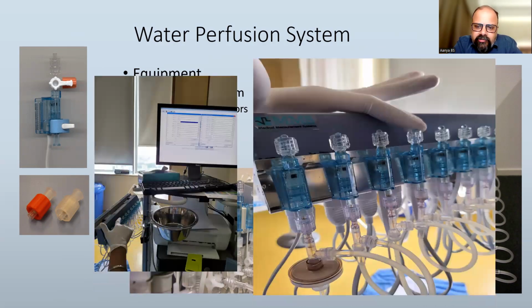The capillaries are the ones you can see right now, and these capillaries can very easily become blocked. Pressure sensors are attached to them, and the water channels inside the catheters can also become blocked, and this is why the problems are in the water perfusion equipment. So you have to make sure each one of these sensors and capillaries is free from any solid particles or air bubbles, and that is why you can't just use them as soon as you join the catheter to them. You have to wait for some time for them to get perfused nicely so that there are no air bubbles and no solid material running through them.